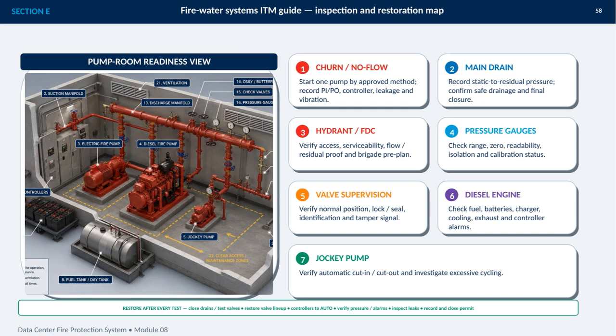First, start one pump using the approved method, then record pressure at the inlet and outlet, along with controller status, leakage, and vibration. Next, perform the main drain check by recording the change from static to residual pressure, while confirming safe drainage and complete closure.